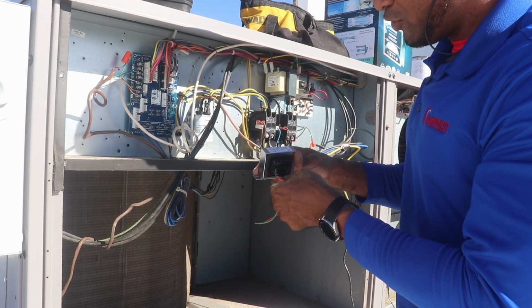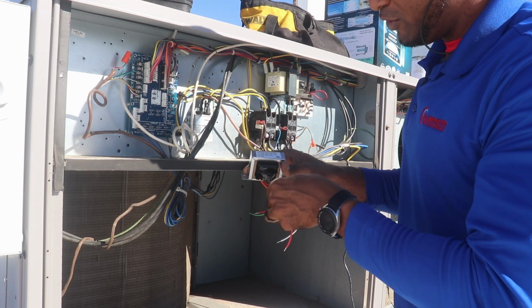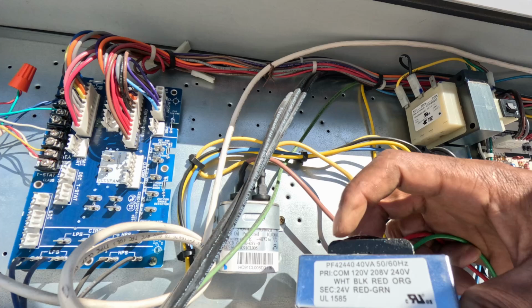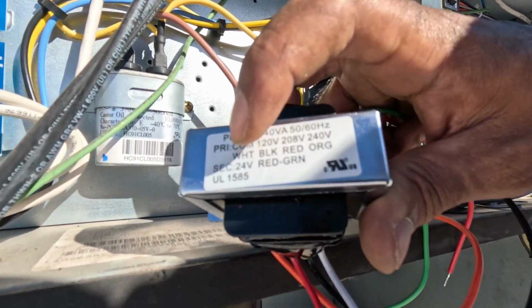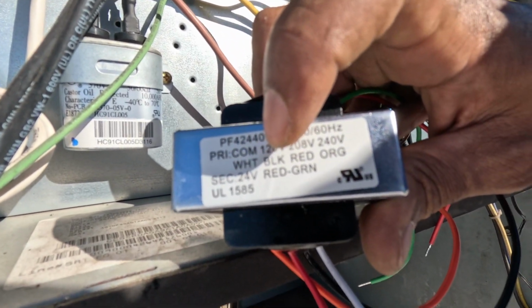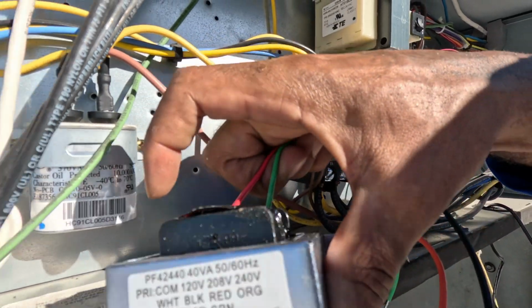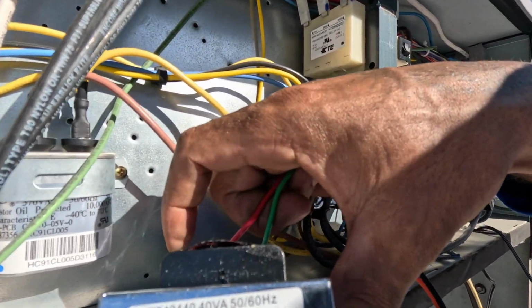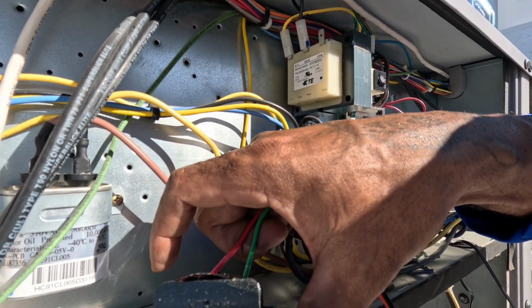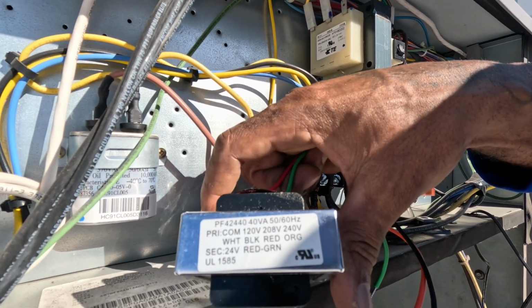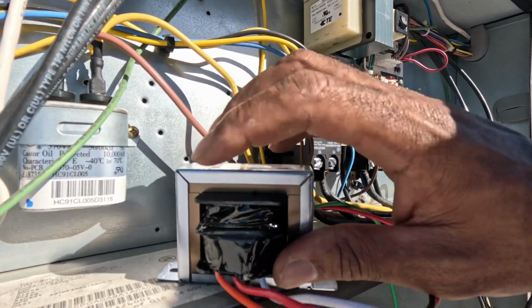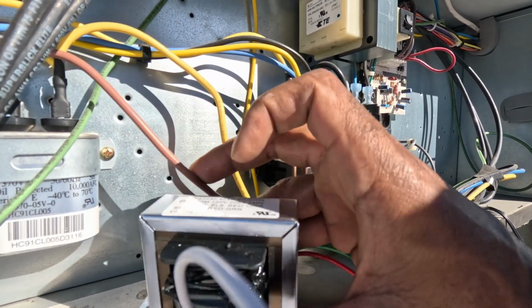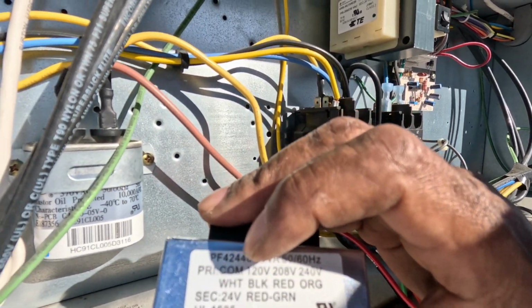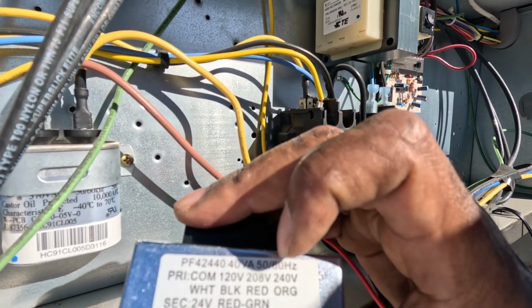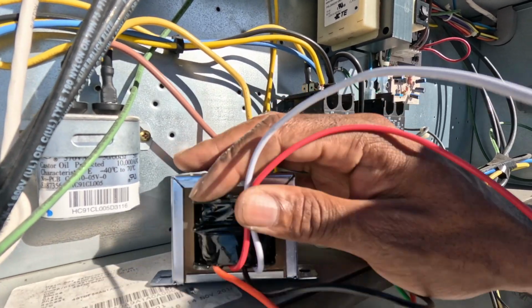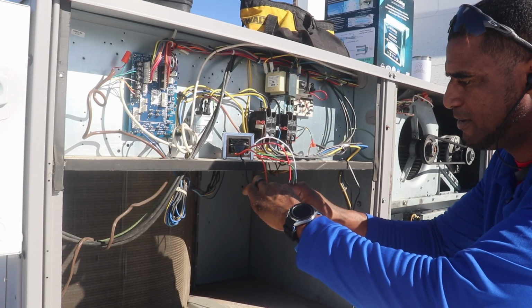My red is 208, so the only two wires I'm gonna use are white and red, these top two, which go directly to my air scrubber. The white is the common for the primary and the red is the 208, so I'll just be using those two. I'm gonna cut the black and the orange, or just cap them off to get them out of the way.